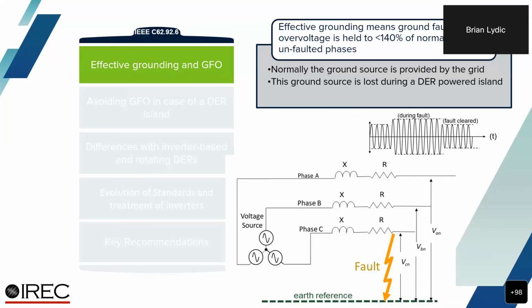So you've got 3 phases on the distribution system, and one of those has a ground fault, like a tree branch is hitting the line, or a line is down hitting the ground, something like that. In that case, the ground source is normally provided by the grid, so there's grounding throughout the distribution circuit that keeps the faulted phase grounded, and keeps the other phases referenced to ground and neutral. However, if you do have a fault, then you might have a switch on the distribution system open up. And then if you've got DER feeding that side of the switch, they could be feeding the fault and energizing the other phases.